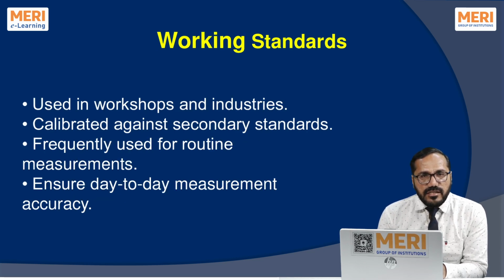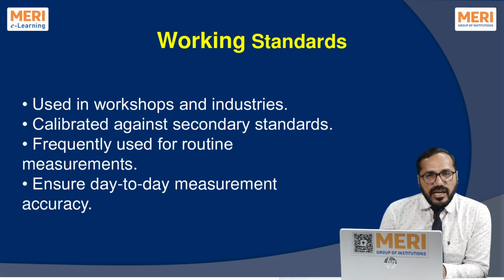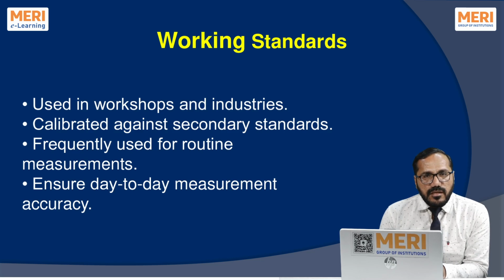Working standards. These are the standards used in industries and workshops for everyday measurement activities. These are the standards that production engineers, technicians, and quality inspectors use regularly during manufacturing and inspection processes. Working standards are calibrated against the secondary standards at fixed intervals, such as every 6 months or 1 year, depending on usage. This ensures their traceability and maintains the accuracy in routine measurements.